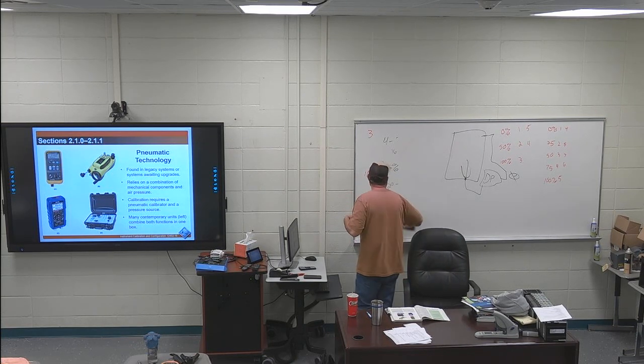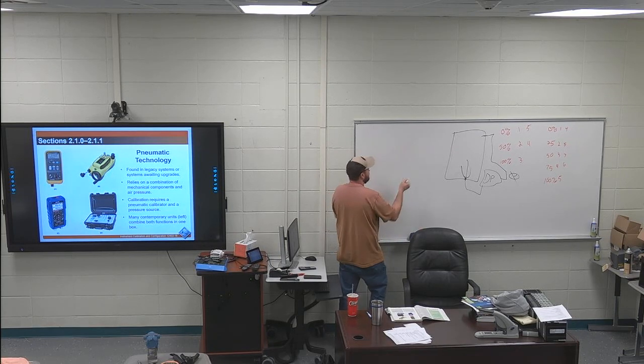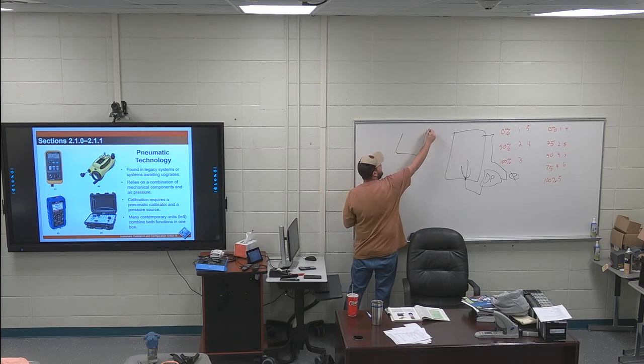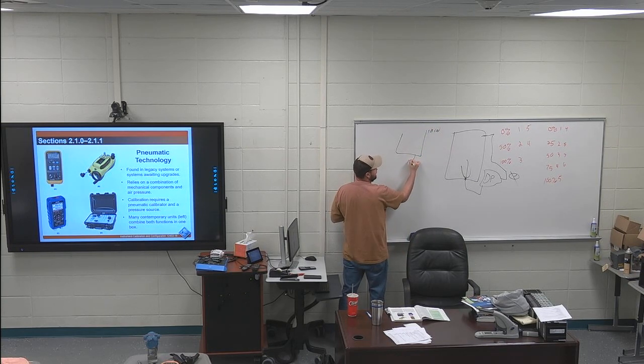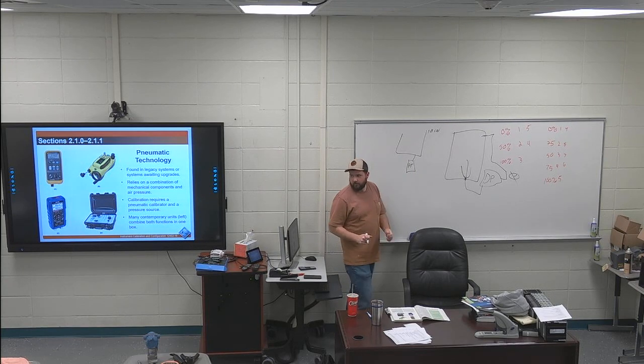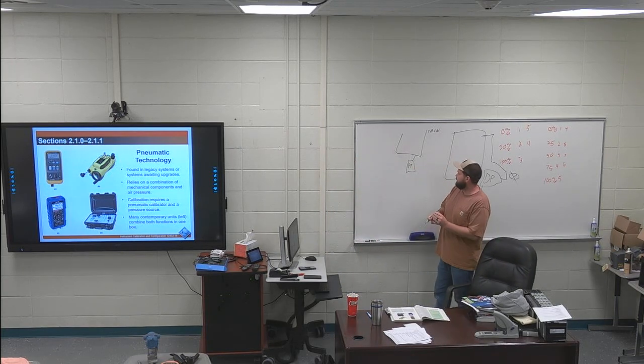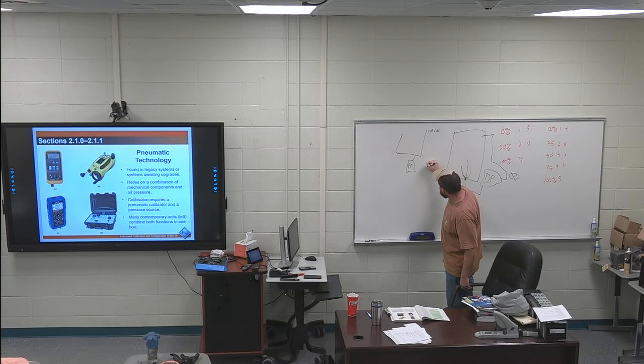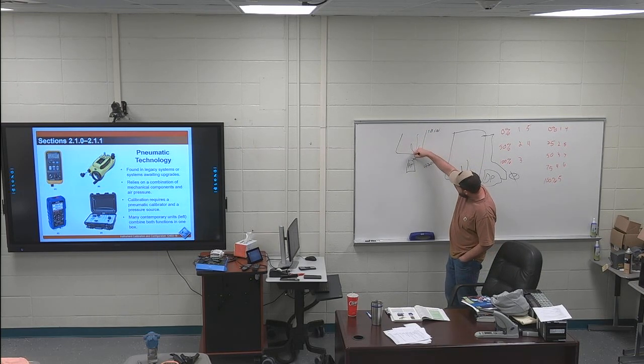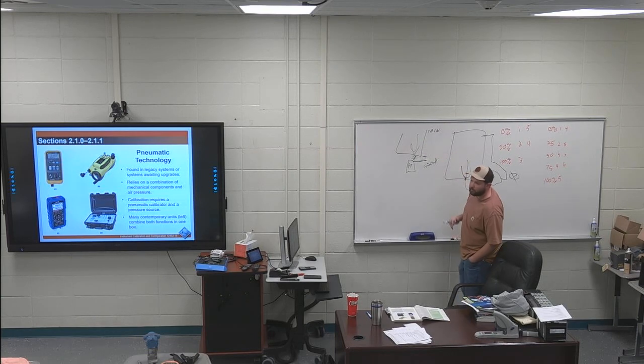So literally on that trainer tank out there, you got a tank that's open atmosphere at the top, and you got like 10 inches, and you have a pressure transducer right here, right? This pressure transducer puts out a 4 to 20 milliamp signal based on how much fluid is pushing down on this. This has a little connection piece right here, so the actual sensor is right here, right? And I'm measuring this as my 0 of the tank, because that's the bottom of the tank, right? So this is called a suppressed 0.